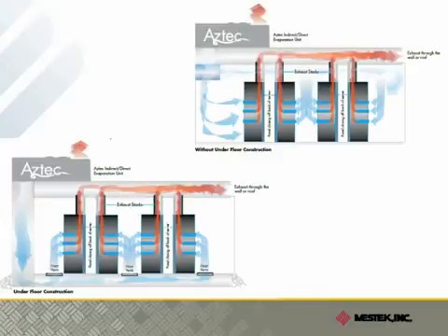But if you use the Mestek Aztec indirect direct evaporative cooling system combined with hot aisle containment, a fancy way of saying you need to capture the heat off the back of the server rack and get rid of it instead of recirculating it, then you can change the PUE picture significantly without impacting the operation or reliability of the servers.